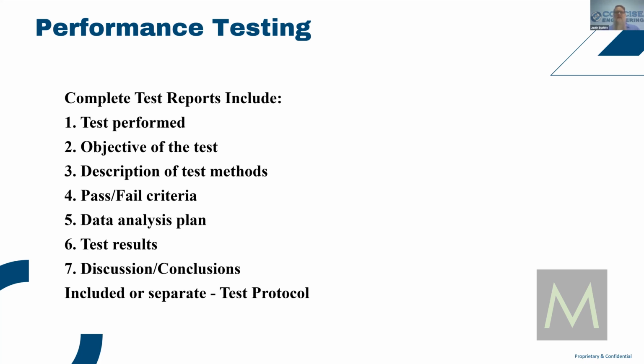So a lot of times you still need to write a wrapper around the report that will describe what they tested, why they tested it, what the issues were. One of these, probably a decade ago, they did a release and they had undefined EMC requirements that you had to define. And so if you don't define those ahead of time, you don't have true pass-fail acceptance criteria.